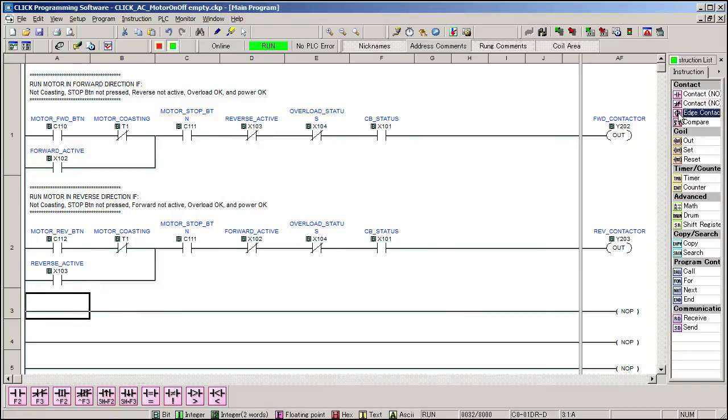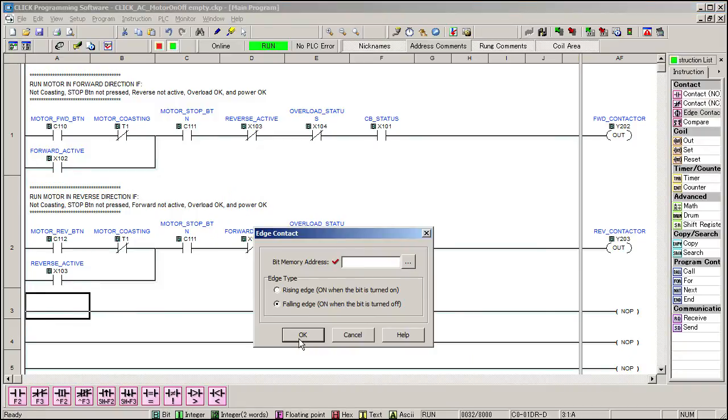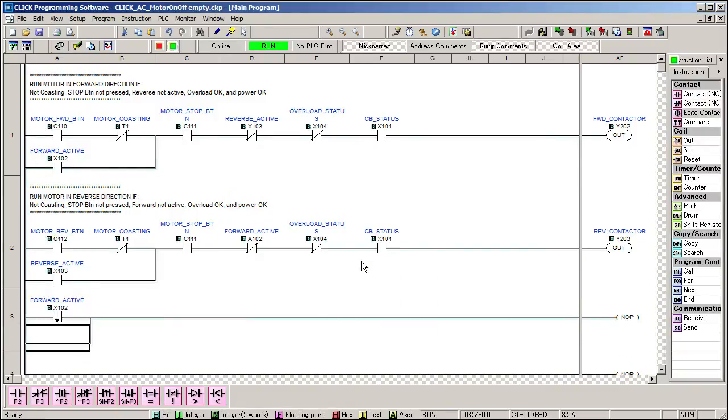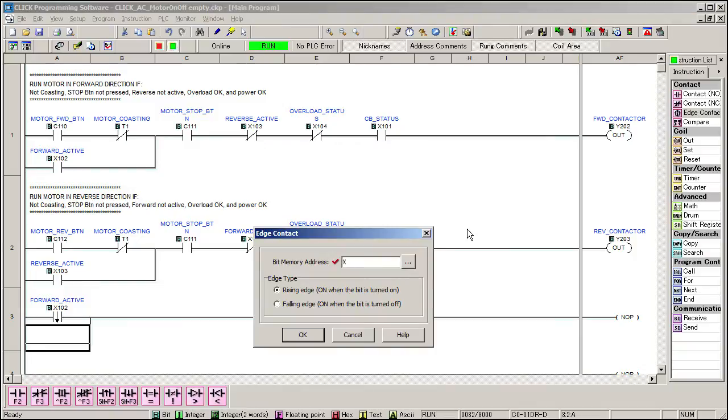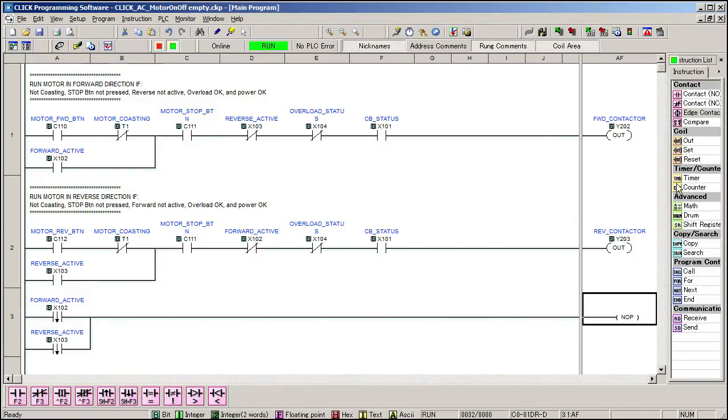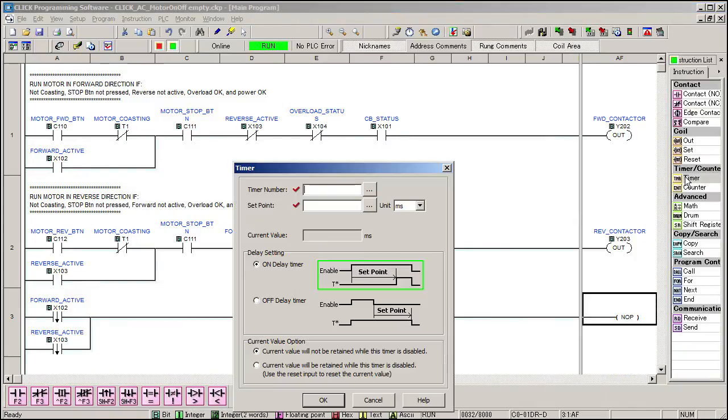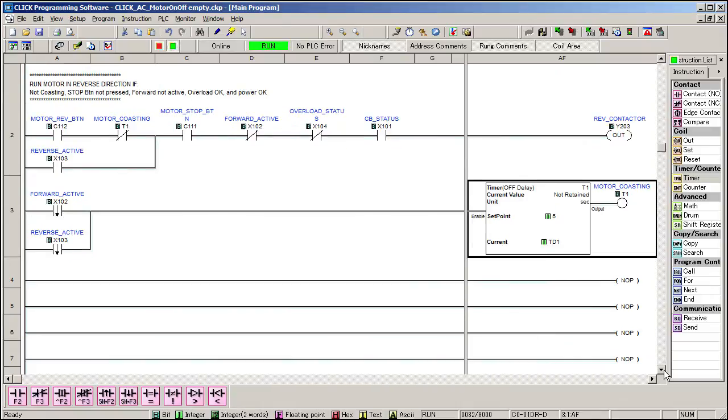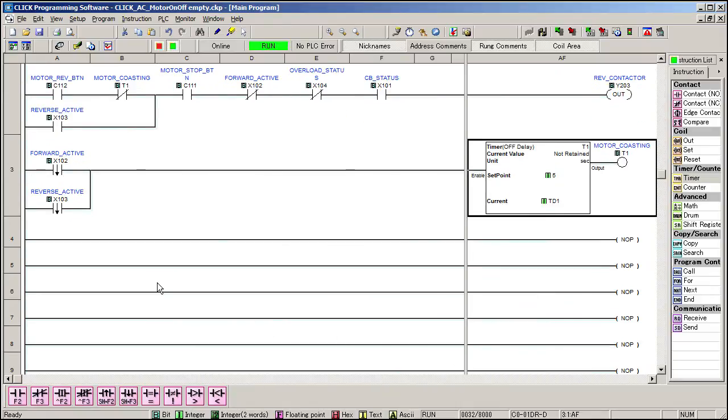We need a 5 second timer for the motor spin down, so we'll watch both contactors AUX contacts and if either of these gets released, we'll start an off delay timer. That starts a timer after the input has been released and sets the T1 bit while it is counting down the 5 seconds. We'll use that T1 bit to tell us when the motor is coasting. Now we can use that motor coasting bit to create the flashing stop indicator.